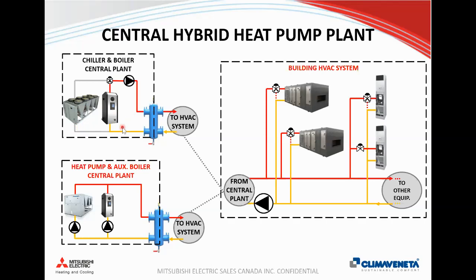So the important thing about a two-pipe system is we're only ever supplying either hot water to all the units in the building, or we're supplying only chilled water to all the units in the building. If we have four-pipe systems, that's really just two-pipe systems stacked together, where one's in heating and one's in cooling, and that's available year-round. You could use these heat pumps in four-pipe systems, but we won't go into those details today. We'll just talk about simple two-pipe changeover systems.